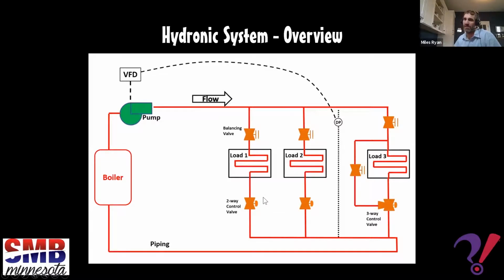As it modulates close, what's that going to do to differential pressure in the system? Well, the differential pressure in the system, that is the difference between the main supply pipe and the main return pipe, is going to start to build. And we're going to measure that differential pressure.